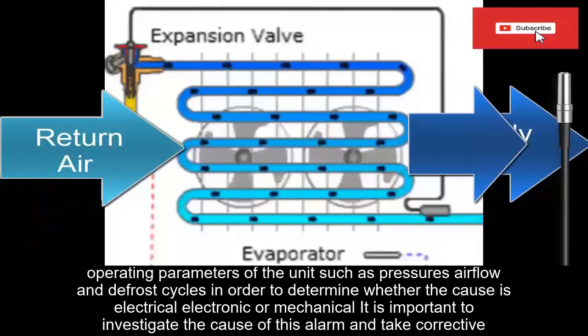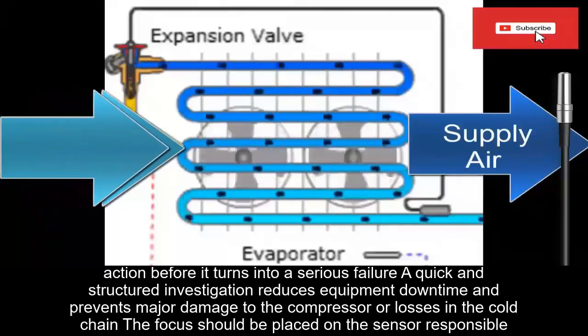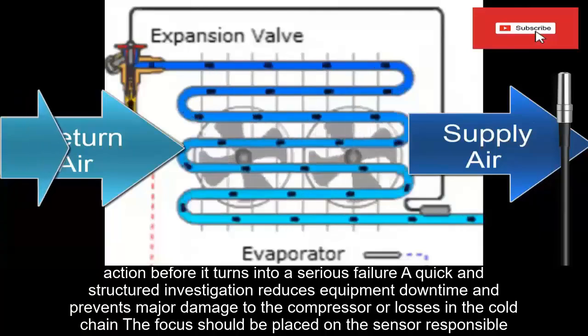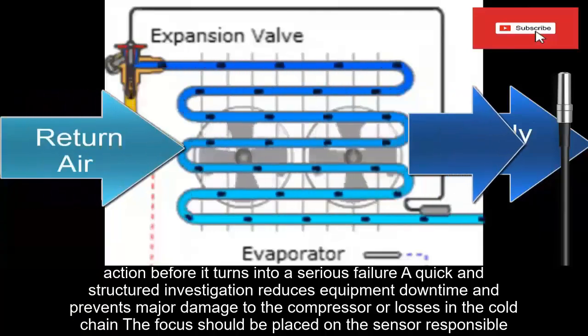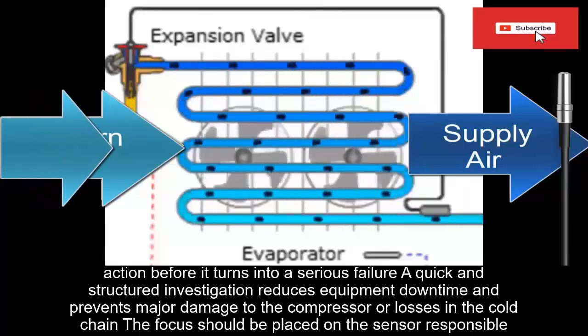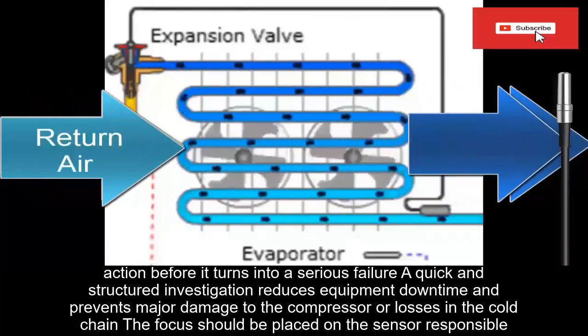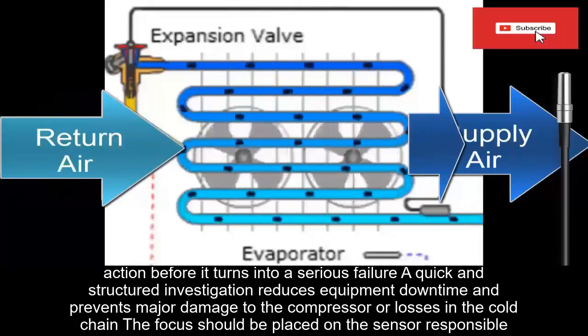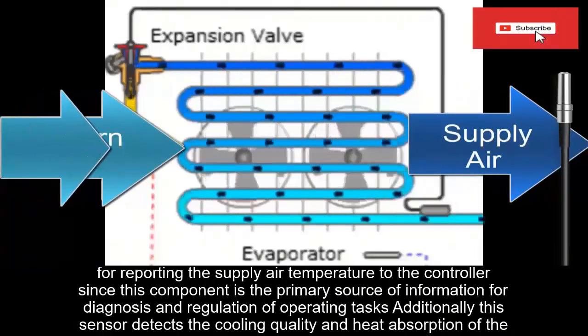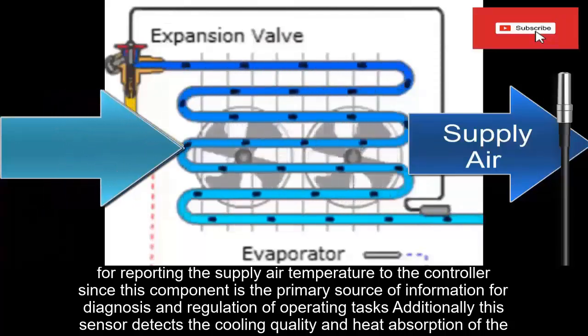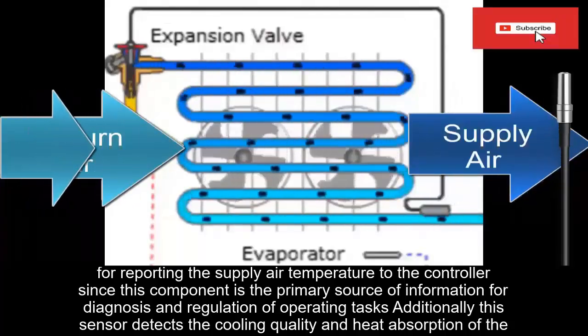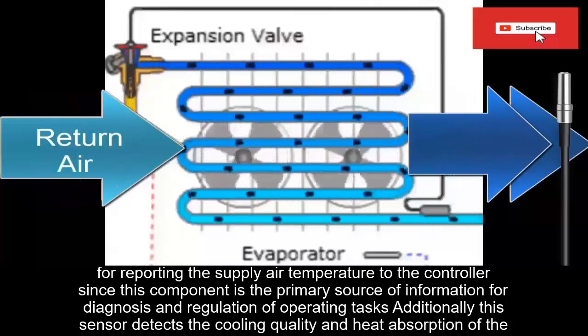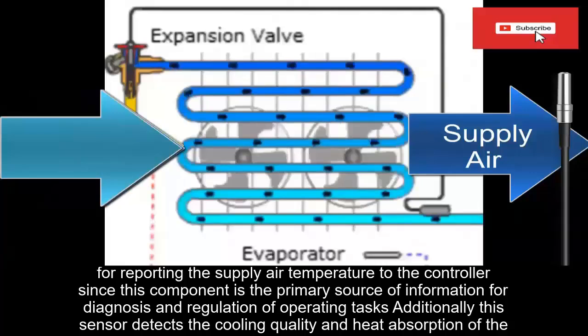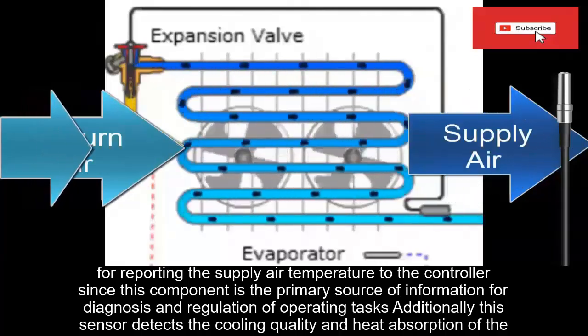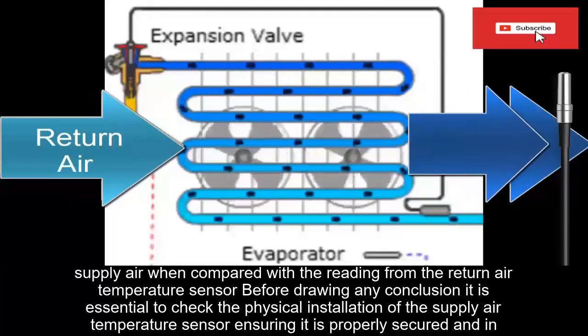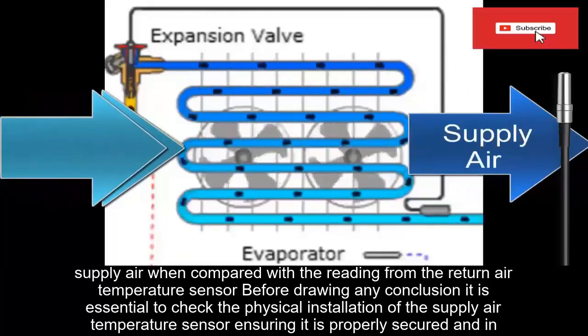It is important to investigate the cause of this alarm and take corrective action before it turns into a serious failure. A quick and structured investigation reduces equipment downtime and prevents major damage to the compressor or losses in the cold chain. The focus should be placed on the sensor responsible for reporting the supply air temperature to the controller, since this component is the primary source of information for diagnosis and regulation of operating tasks. Additionally, this sensor detects the cooling quality and heat absorption of the supply air when compared with the reading from the return air temperature sensor.